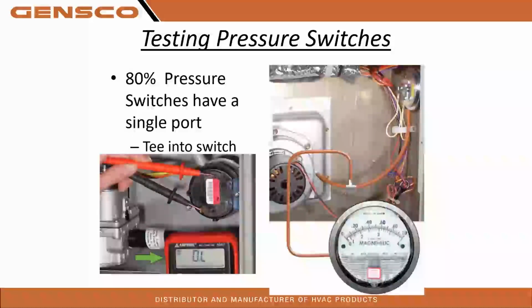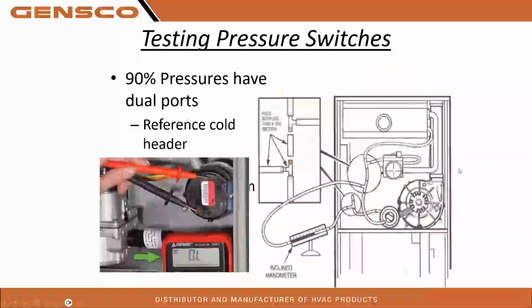We don't want you to have one manometer tube and pull it off and push it on and then go to the switch and go back and forth. Simply tee into it and see what the inducer motor is doing against the pressure switch live. Okay. We should easily be able to make more than the pressure switch rating, provided something isn't hung up.